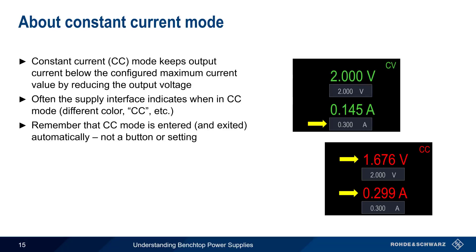And again, it's important to remember that constant current mode is entered and exited based on the readback current value. It's not a button or setting that can be toggled by the user.